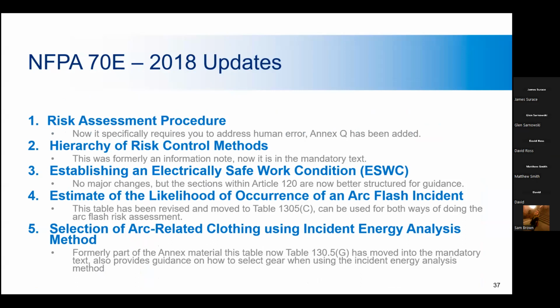So this standard outlines procedures to reduce the risk for inspectors and electrical workers. And here is the way to go through. You start with the risk assessment and you make a list of the hierarchy. There is a hierarchy of risk control methods. You want to make sure you will be able to establish an electrically safe work condition. You would estimate the likelihood of an occurrence of an arc flash incident. Hopefully it's low, because that's very dangerous. And if it is not low, you would choose arc related clothing using incident energy analysis method to make sure that you're safe in the event that an arc flash does happen.